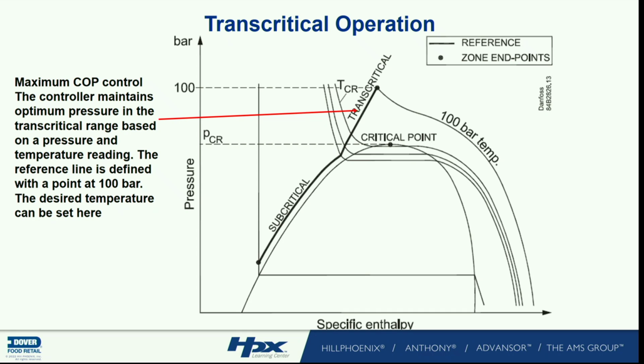Yes, you see where I marked it here? COP curve. So what I'm doing is, as the ambient temperature changes, would you say I'm running up and down the COP curve? I'm here, I'm here, I'm here, depends on how far open he is. And what he's doing is the ambient temperature coming out of the condenser changes, he's moving me up the COP line. Is everybody good?